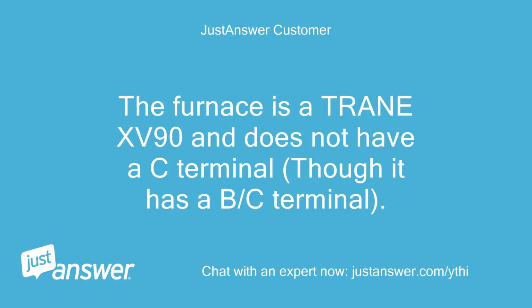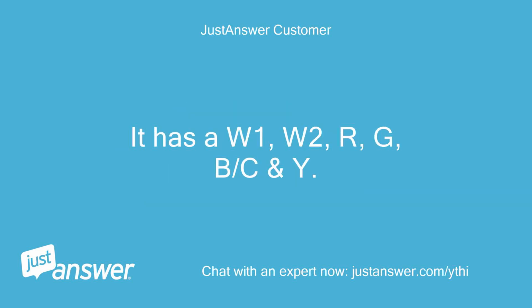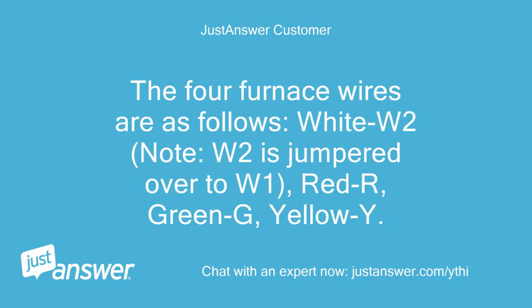The furnace is a Trane XV90 and does not have a C terminal, though it has a BC terminal. It has W1, W2, R, G, BC and Y. The 4 furnace wires are as follows: white W2, note W2 is jumpered over to W1, red R, green G, yellow Y.